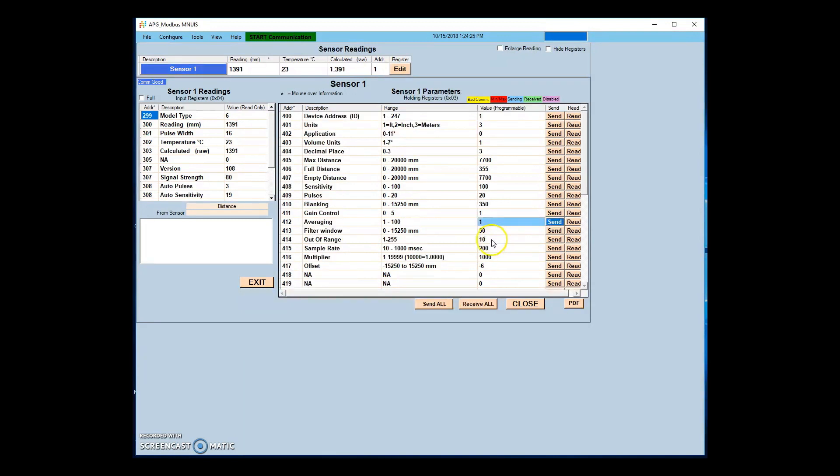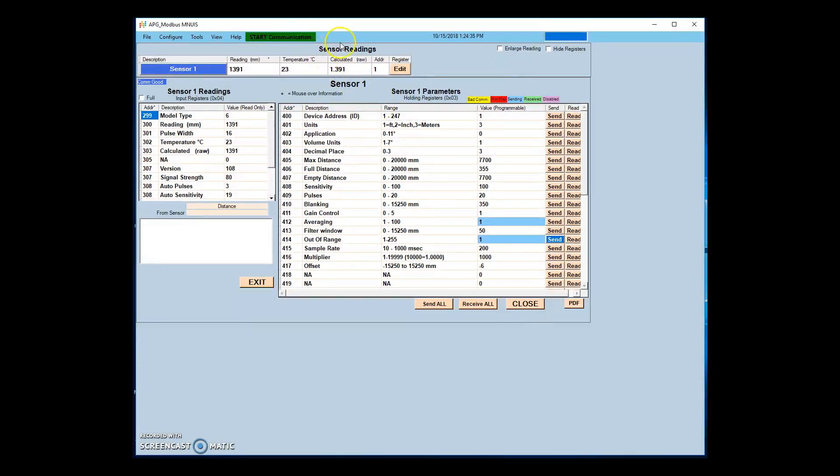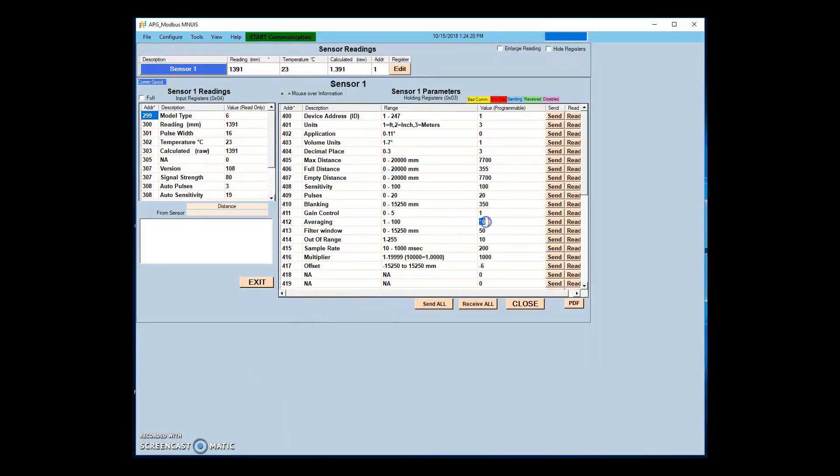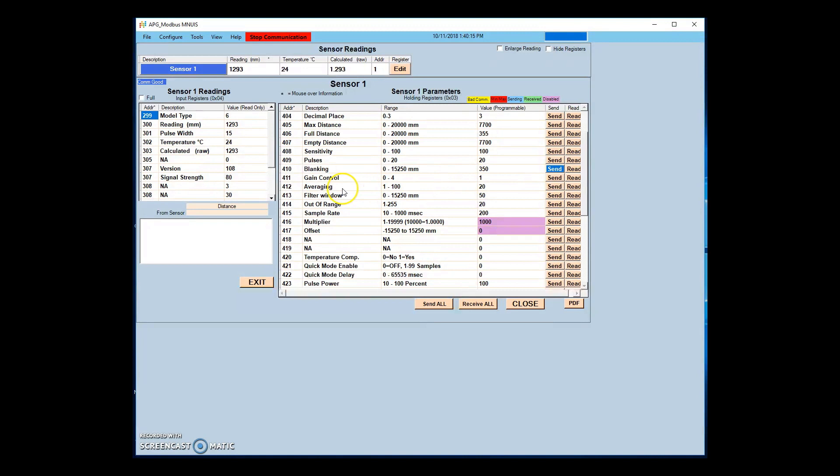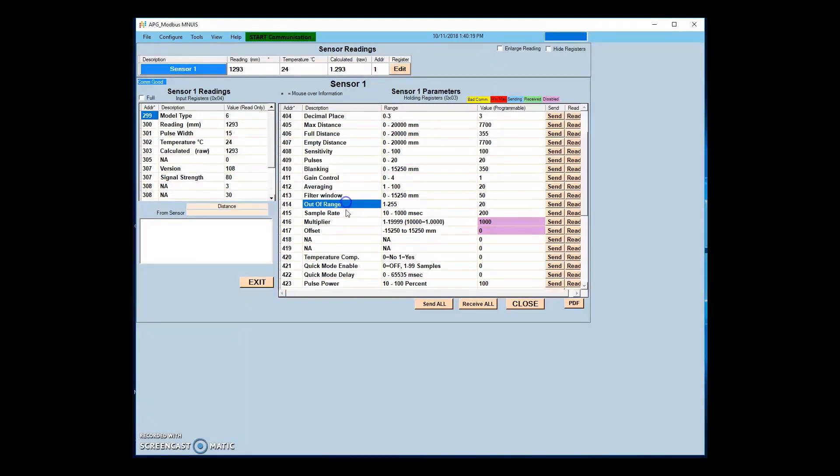The out of range parameter sets the number of consecutive samples outside the filter window that must be received before the sensor will adjust to the new reading. These parameters can be used to prevent false positives from momentary obstructions, such as waves in a tank application, or objects moving past the sensor area.